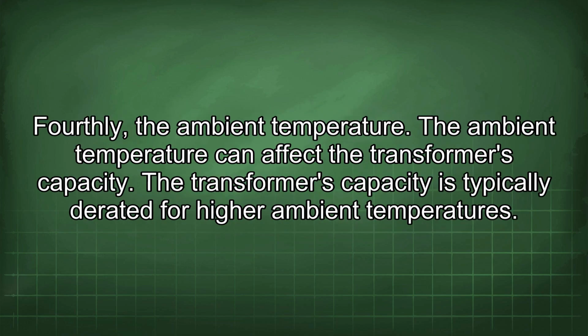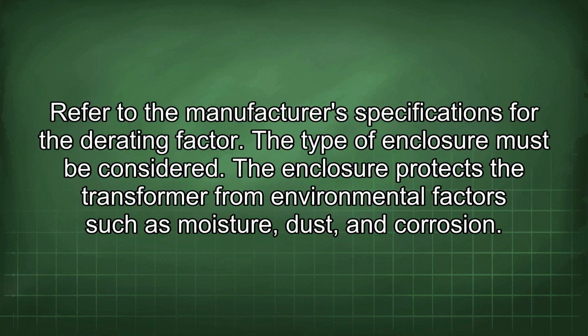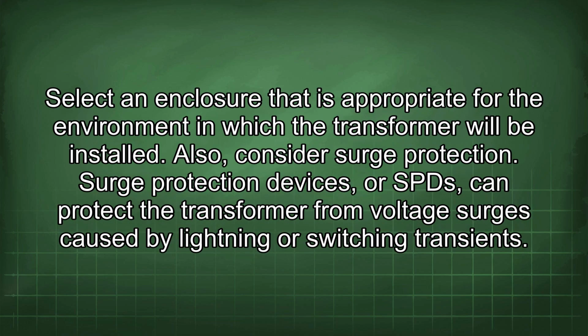Fourthly, the ambient temperature. The ambient temperature can affect the transformer's capacity. The transformer's capacity is typically derated for higher ambient temperatures. Refer to the manufacturer's specifications for the derating factor. The type of enclosure must be considered. The enclosure protects the transformer from environmental factors such as moisture, dust, and corrosion. Select an enclosure that is appropriate for the environment in which the transformer will be installed.